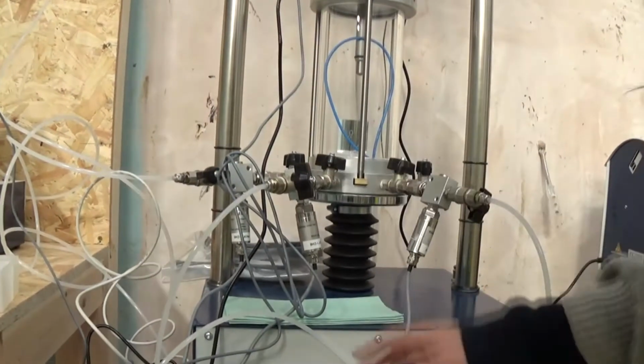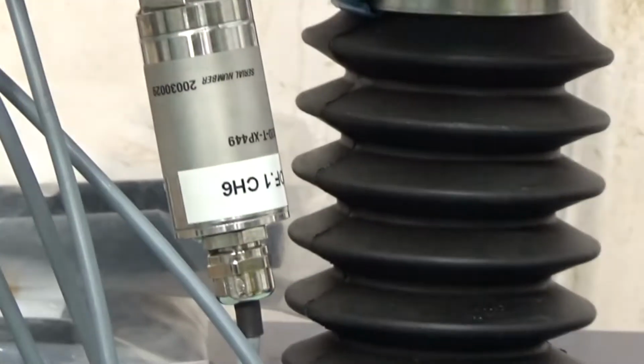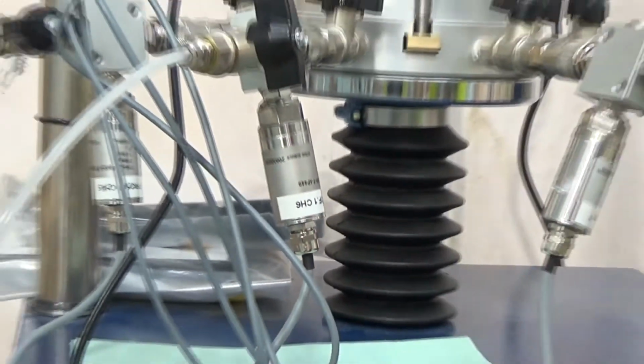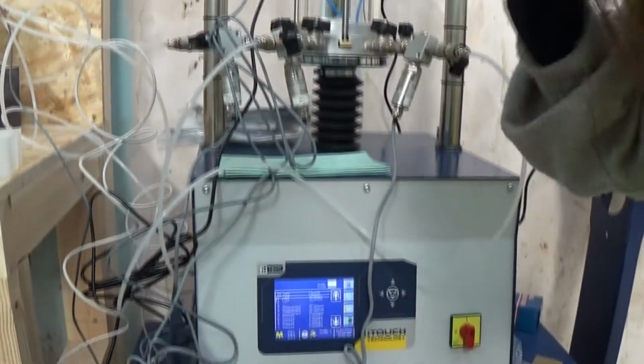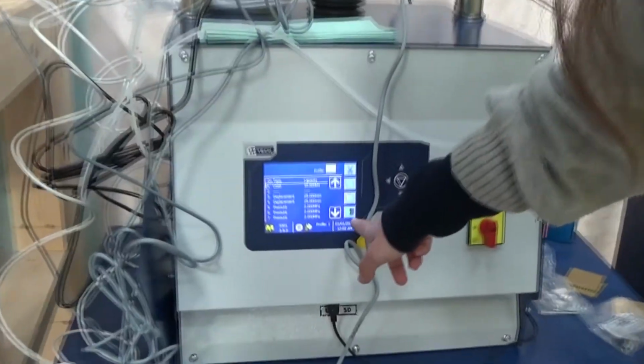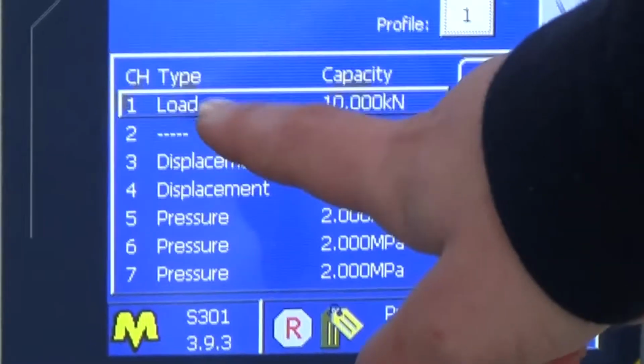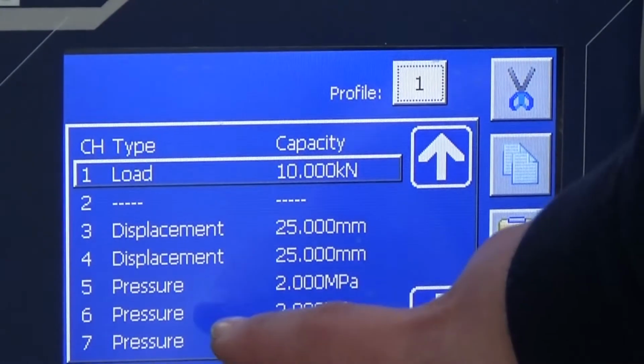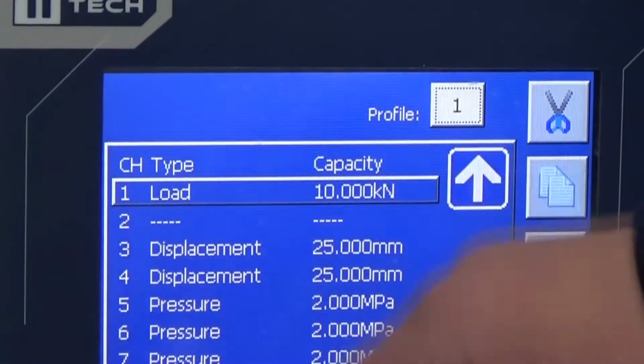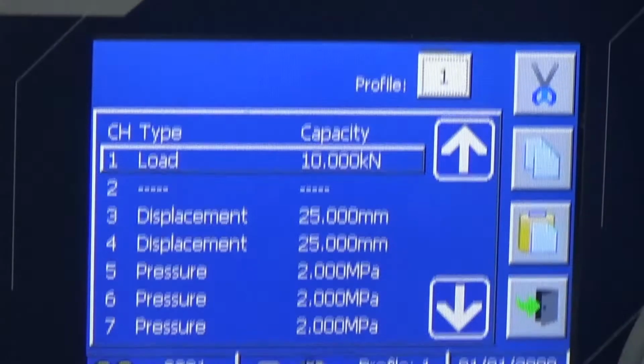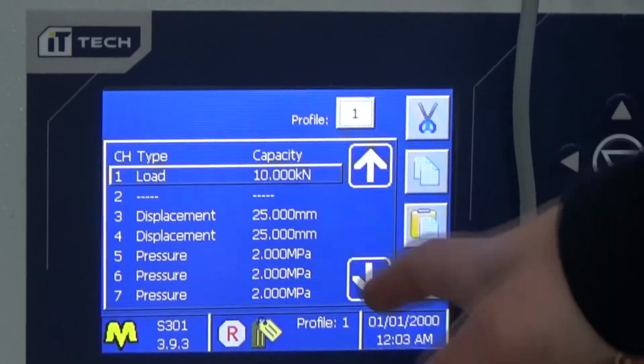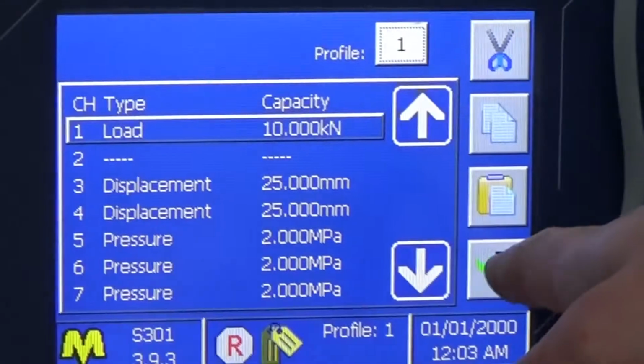You can see here only pressure, but channel 6 is the cell pressure. So you have to record which kind of line of pressure is the related transducer. Because here you can see only load, displacement and pressure. But you have to know which line of pressure and which displacement is related to this channel.